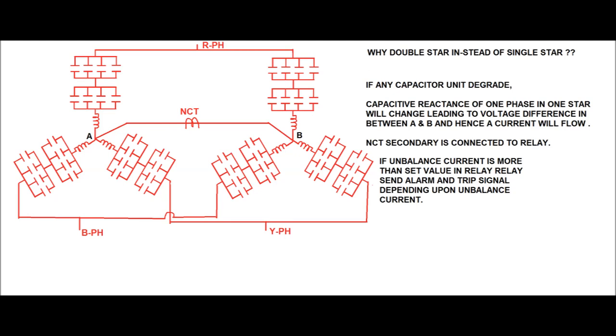Under healthy conditions, the star point voltage of each star connection is zero due to balanced current flowing in each star formation. If a capacitor unit in any phase degrades or fails, the capacitive reactance of that phase changes, causing unbalanced current flow in that star connection. This creates a voltage difference between the two neutral points A and B, causing a circulating current to flow, which the NCT senses.